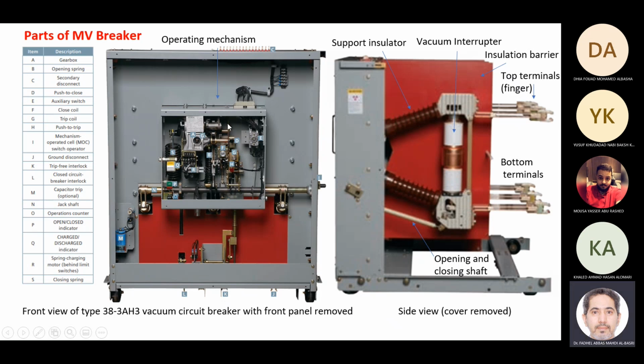You can see here this is the operating mechanism. We have spring 1 and spring 2, one for closing, one for opening. Okay, and so these are the mechanical springs we have, and on the other side we have the front view in the panel, and this is the side view. This is the breaker interrupter, which is a vacuum tube now. I'll come to this, what's inside vacuum tubes.